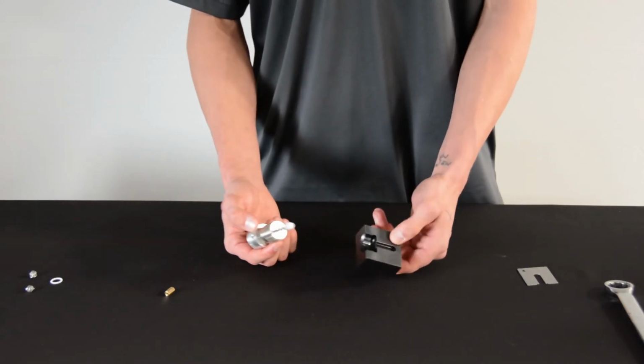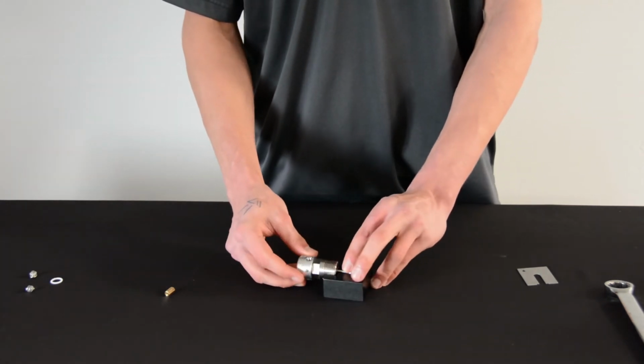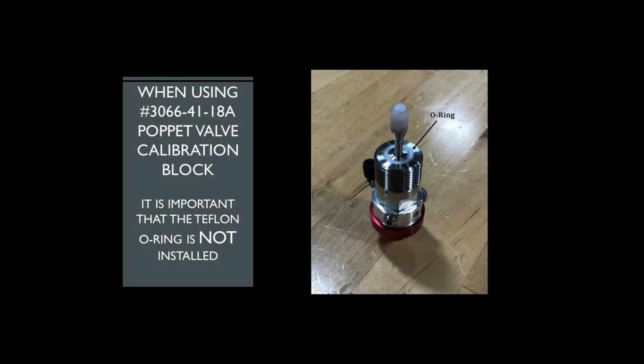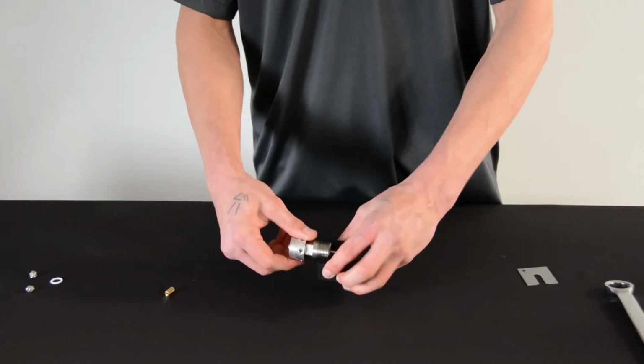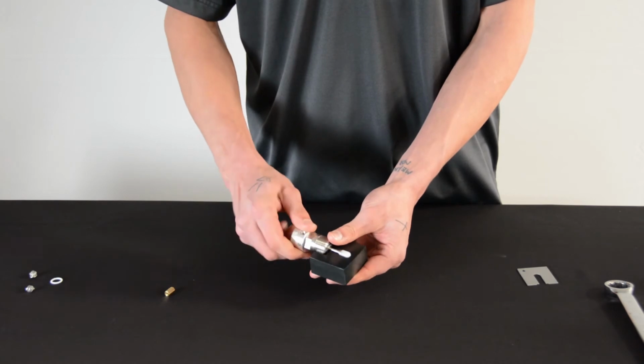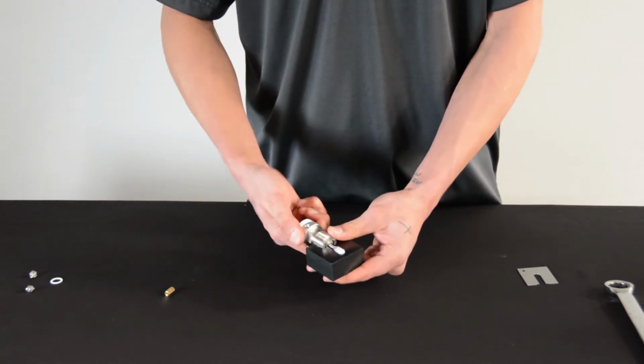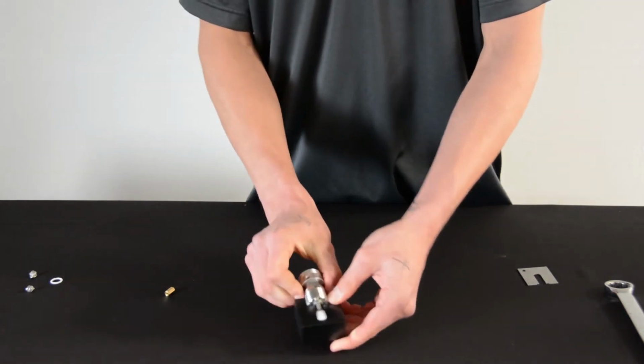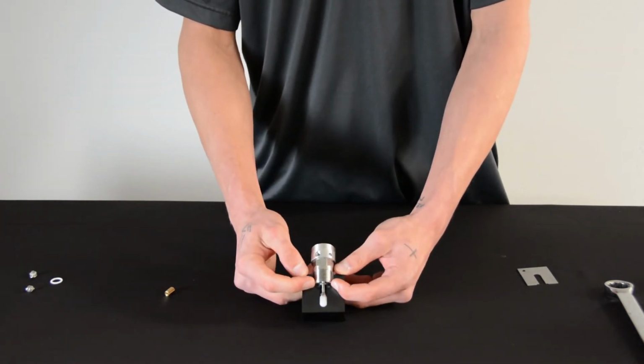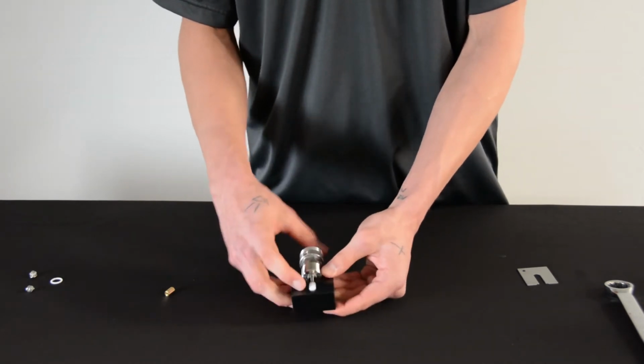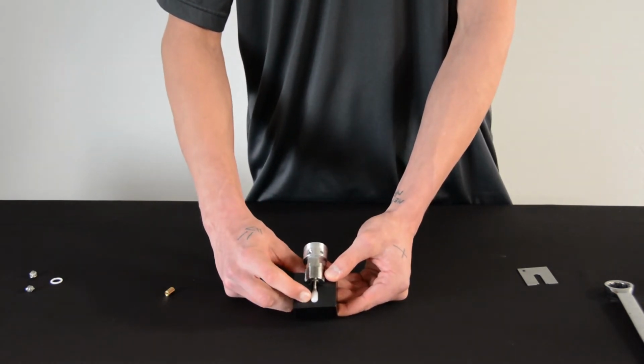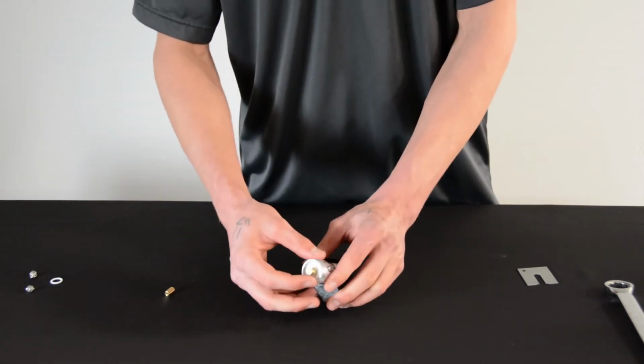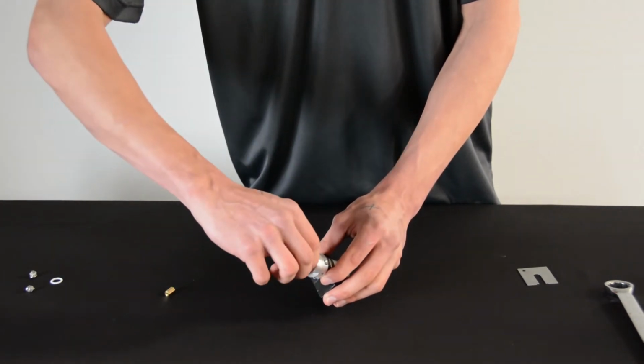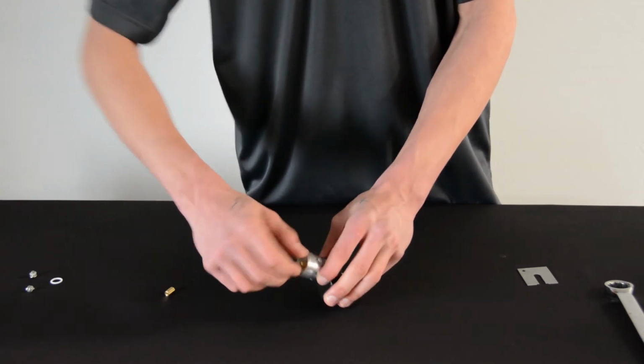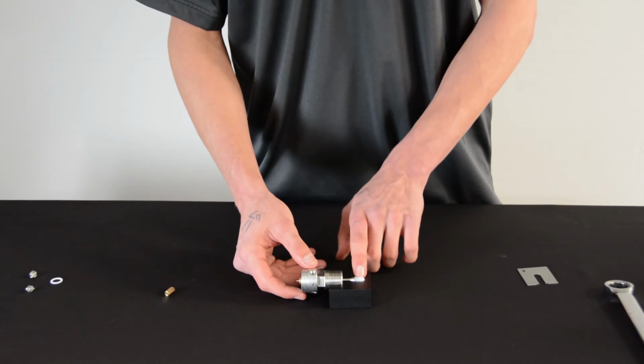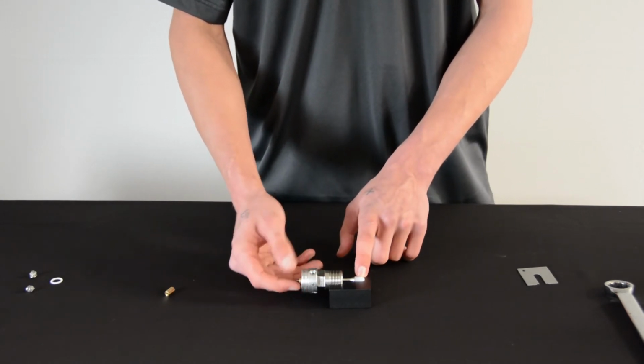To use the Poppet valve calibration block, you're going to put your Poppet valve in and thread it in until the valve body is fully seated up against the bottom of the calibration block. Then make sure your plunger end is fully seated in the calibration block and finger tighten your piston retaining nut against the piston. It is important not to over tighten, as this will pull your plunger end off the bottom of the calibration block.